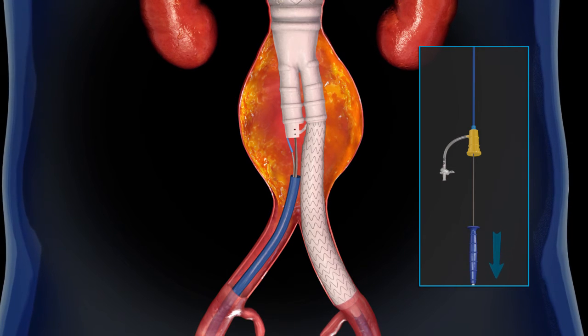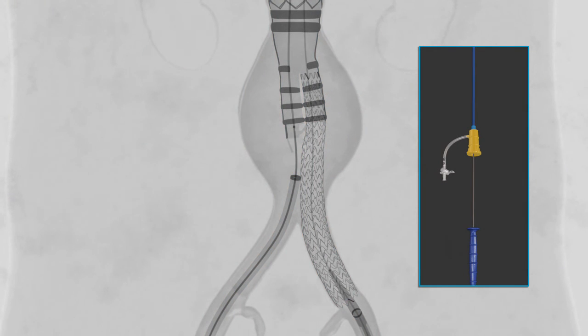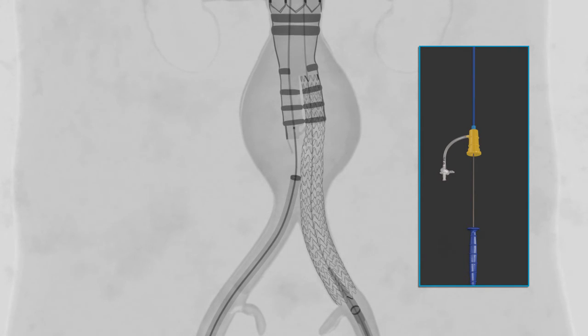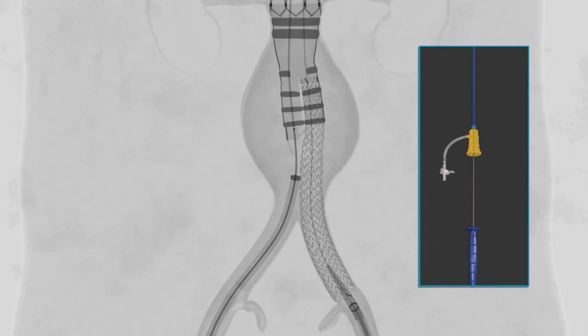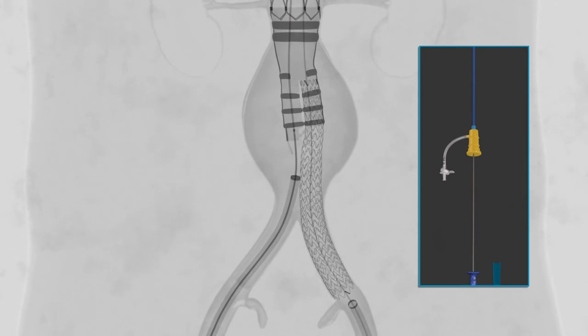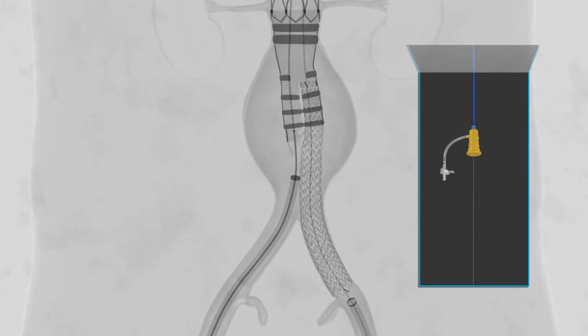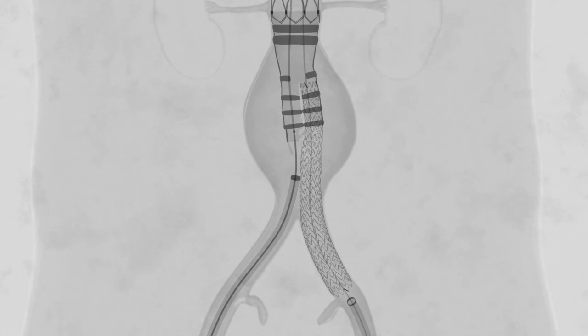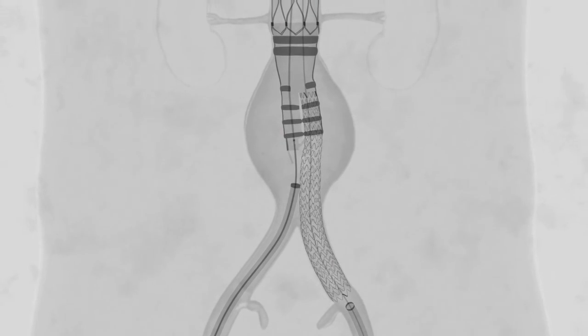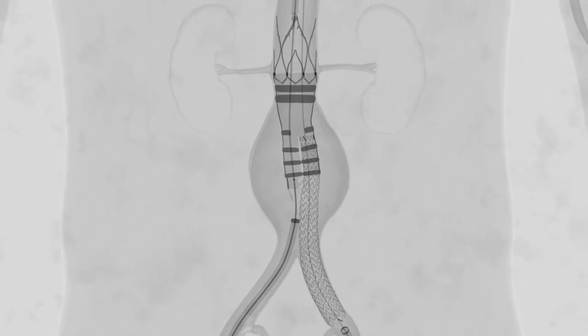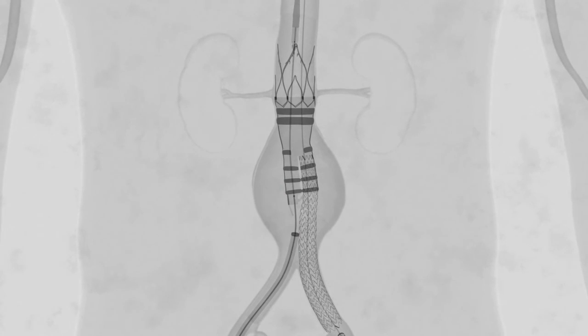The Ovation IX delivery systems are equipped with an integrated leave-behind sheath and hemostatic valve. If utilized, the entire system is repositioned to the desired location. Keeping the guide wire in position, the handle is retracted to remove the inner catheter from the outer sheath. The delivery system can also be removed completely. A minimum of 14 minutes after fill polymer mixing, the aortic body can be released from its delivery system.